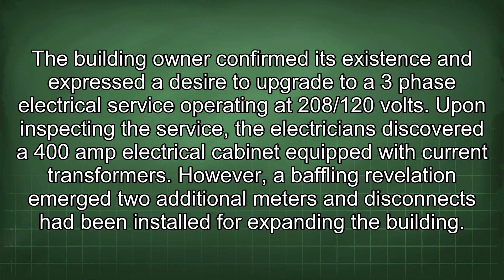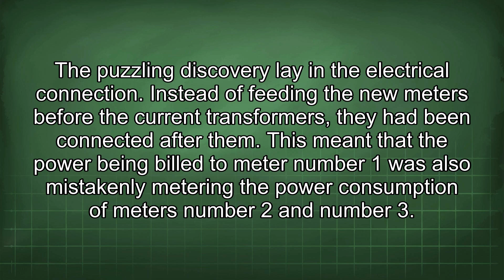However, a baffling revelation emerged: 2 additional meters and disconnects had been installed for expanding the building. The puzzling discovery lay in the electrical connection. Instead of feeding the new meters before the current transformers, they had been connected after them. This meant that the power being billed to meter number 1 was also mistakenly metering the power consumption of meters number 2 and number 3.